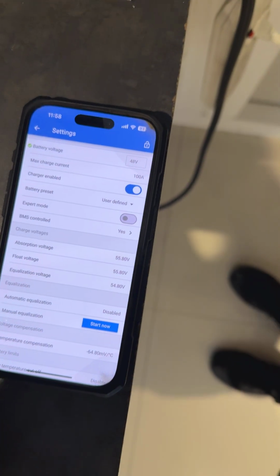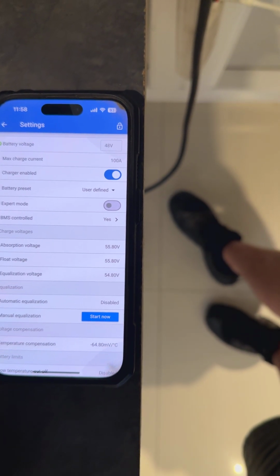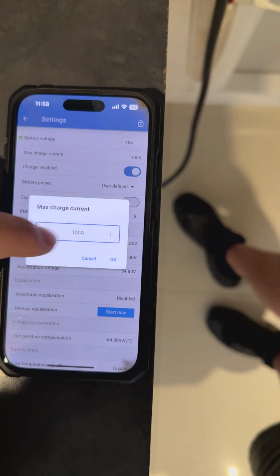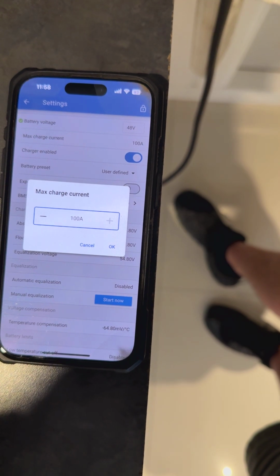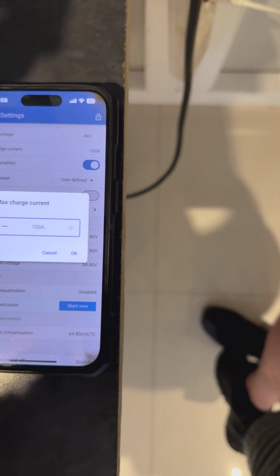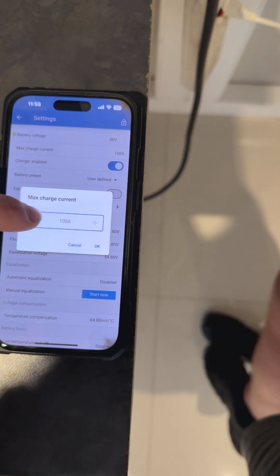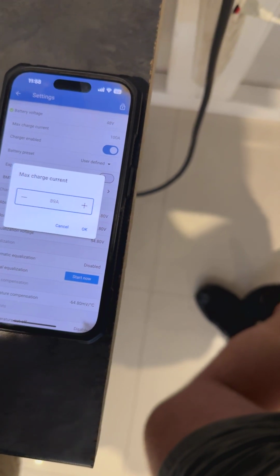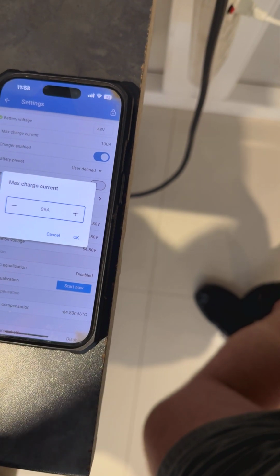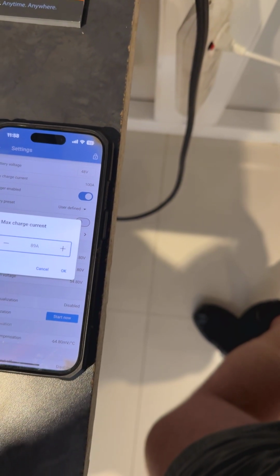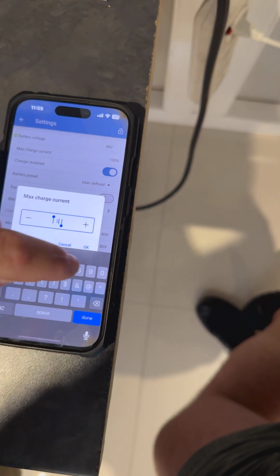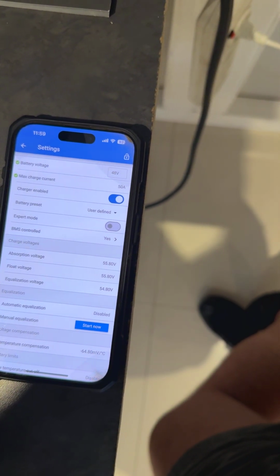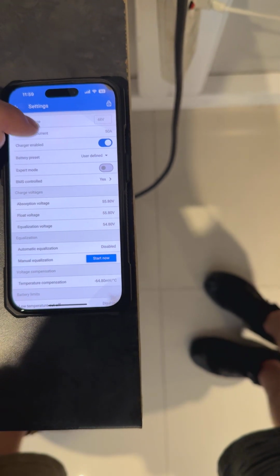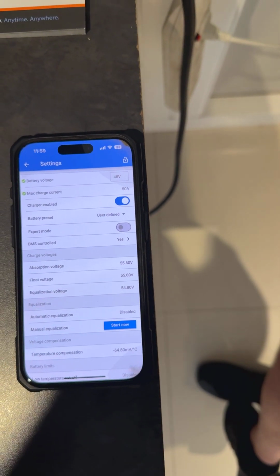The rest of the settings are quite easy - just your maximum charge current for the system. You can't set this higher than the product's actual maximum; this one is a 250/100. You can set it lower if you don't want to charge at full capacity, or if you have a single battery now but plan to add more in future with a bigger MPPT - for example, you could set it down to 50 amps.